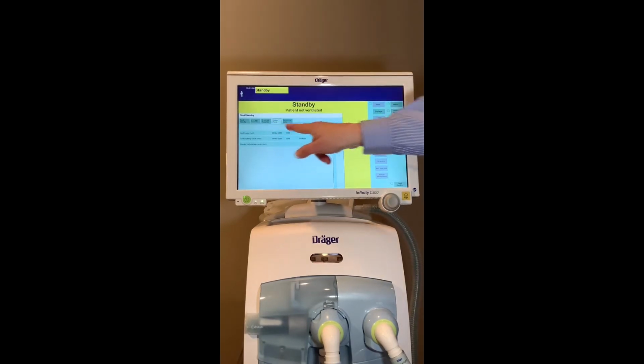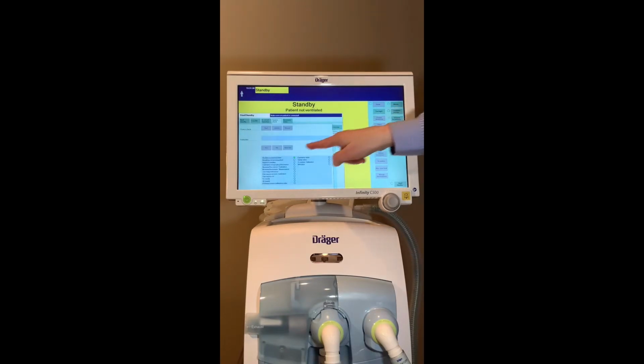Within the System Check window, the first tab you find is an overview of the last test that was performed and the status. This is where you'll also find the tabs for the device check, which goes through and calibrates all the different components of the ventilator box, as well as the breathing circuit check, where the user can do the breathing circuit check or leak test.